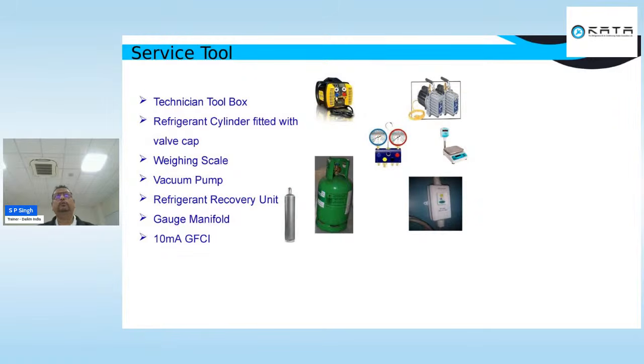When we talk about service tools, we should have recovery equipment. When we talk about 410, it is a combination of two refrigerants, or even if we talk about a single refrigerant, a recovery cylinder and a recovery machine should be there. We should start using recovery equipment. Today awareness of recovering refrigerant is very low. Though it might be an expensive product to buy, we should start using a recovery system, so that we can collect that refrigerant in one cylinder, and then either dispose of it, or if you feel that refrigerant is proper, reuse it.